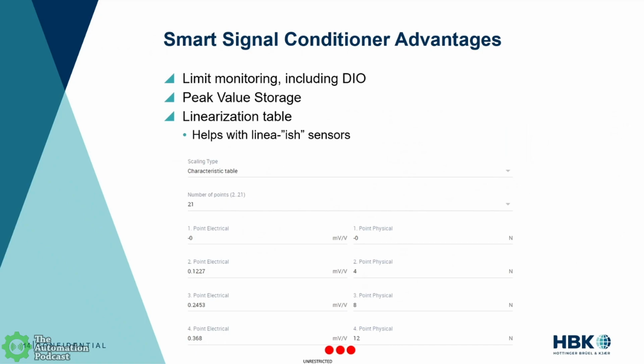And then one of my favorite, or what I think one of the really powerful functions of a smart signal conditioner like the ClipX is this ability to add in a linearization or a characteristic table. I like to say this helps with linear-ish sensors, right? Every time you buy a load cell, you're buying it under the presumption that there is a perfect linear relationship between the 0 point and the full scale. You might get a test certificate that has 0 load, 100% load, and even if you get a test certificate or a calibration cert that has 6, 8, 11 load steps between 0 and full scale, with something like an old school more analog signal conditioner, you really can only adjust for that 0 point and that full scale point.